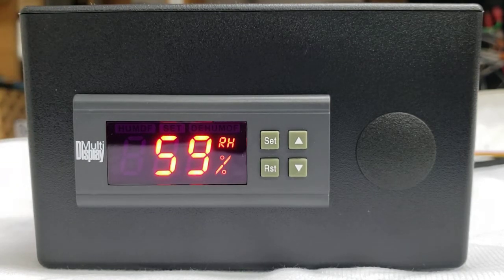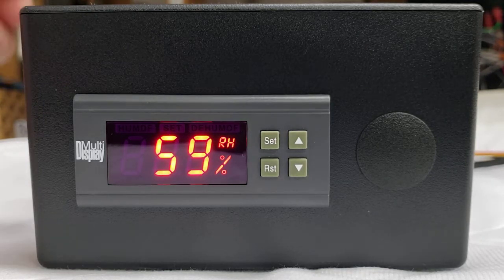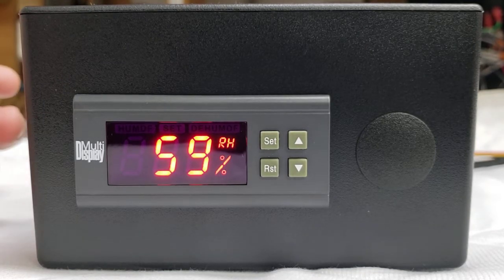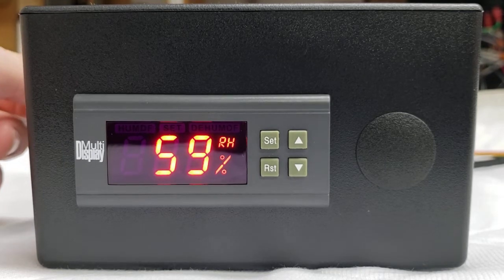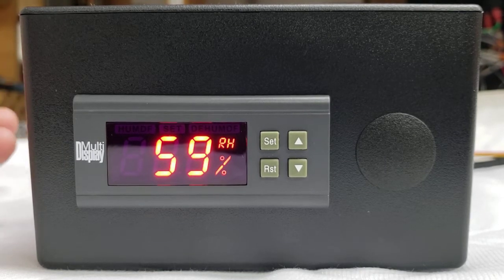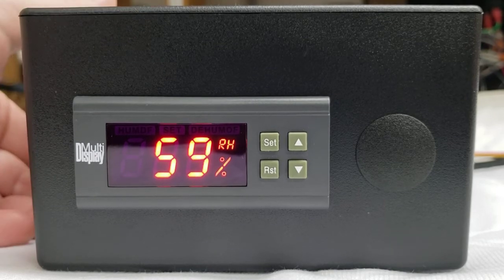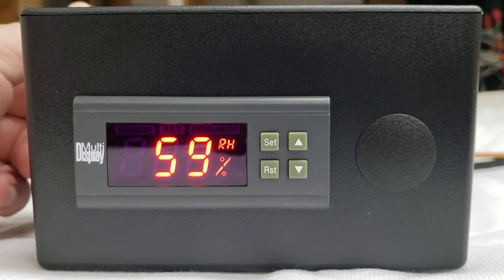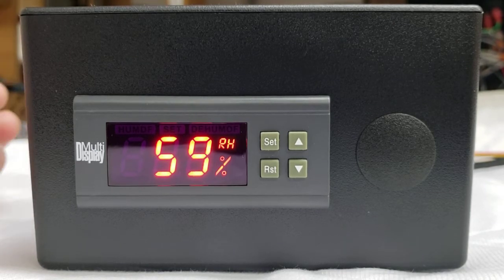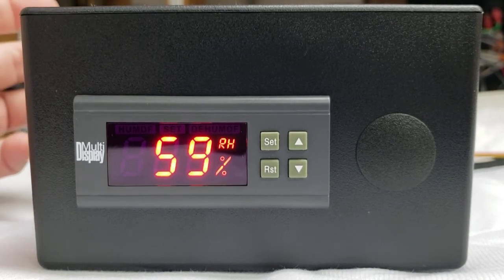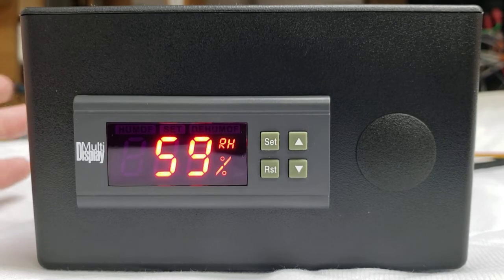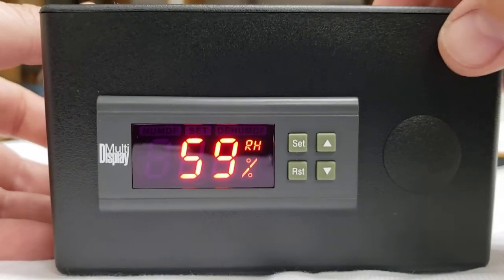Now this also covers the model that we use for the hinge door and the previous Clearview incubators. The humidity controller really hasn't changed much across these, so the settings are basic. On the new model, we actually have the instructions printed right on the top of the controller box. But if you've got an older style and the instructions weren't on that box for the hinge door models or Clearviews, I want to run you through what the settings are.